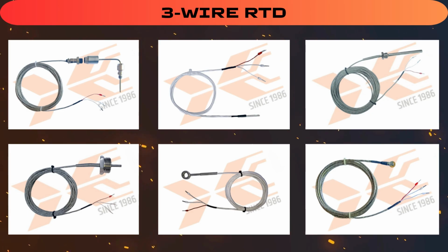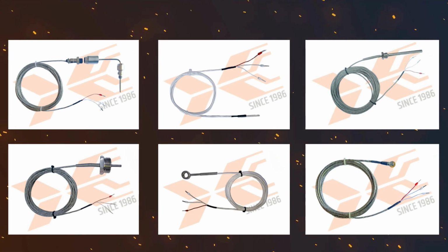Advantages: great balance between accuracy and cost. Works well in industrial process control. Compatible with transmitters and PLC systems. Disadvantages: slight error if the wires are not perfectly matched in resistance. Requires special instruments that support 3-wire measurement. Typical use: process plants, machinery temperature monitoring, and automation systems. Pro tip: for best results, always use equivalent wires and the same wire gauge for all 3 leads.